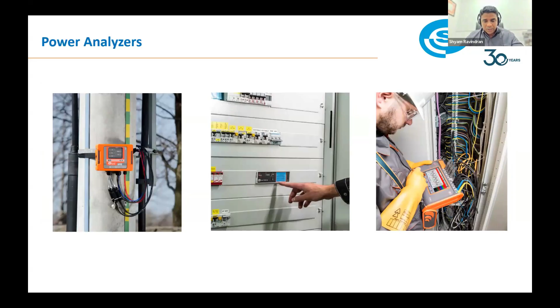This is our recent change on the PQ device. We moved from a portable device—well, we still have a portable device, but we've improved from portable devices to a permanently fixed device. This is important because the regulation was emphasizing continuous monitoring, with no need for software to be required by the users. So the regulation says it must be permanently installed and must be accessible by the authorities or clients at any instance. It must be continuous—that is the primary reason for us to bring out this kind of solution.